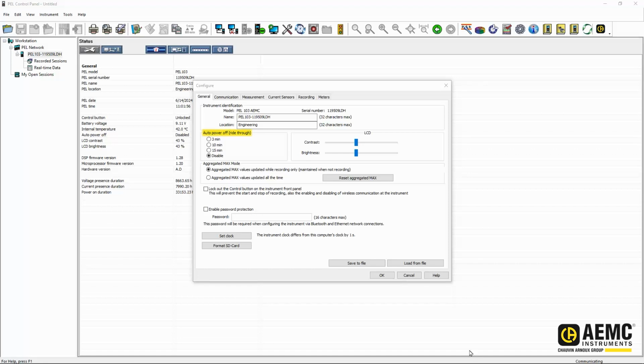The auto power off function will power the instrument down after the selected interval if the PEL should experience a loss of power. Disabling this feature allows the PEL to operate as long as the internal battery has enough charge, which is about 30 minutes. Next to the power off selections, we can adjust the screen brightness and contrast if needed.